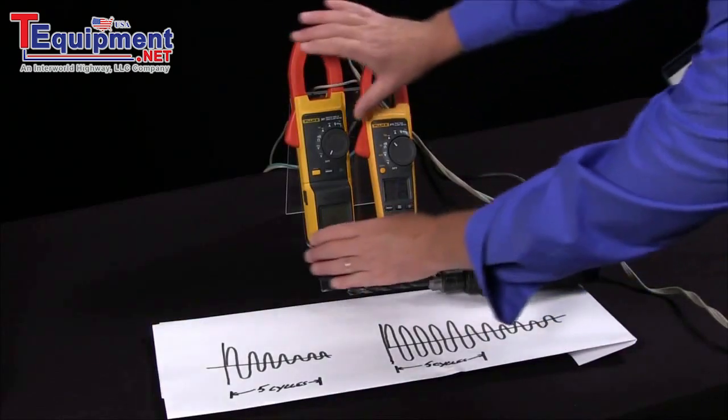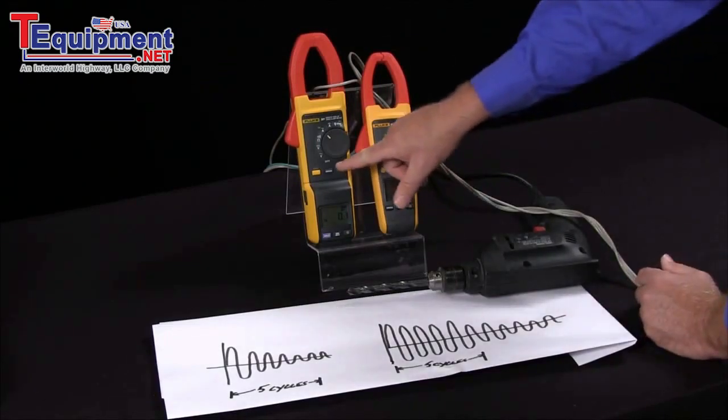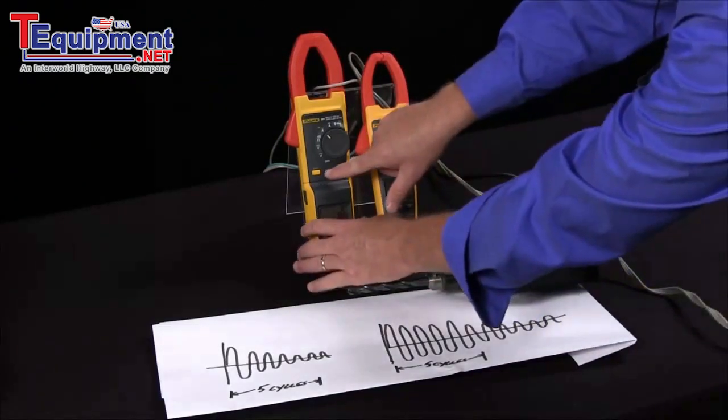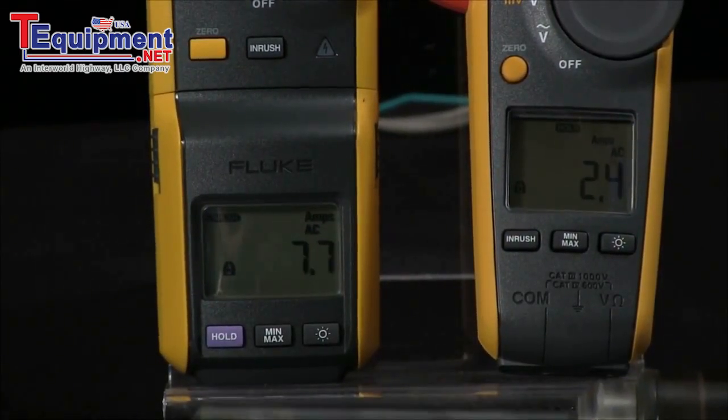Well, to take an inrush current I would turn on my meter to amps and I would need a clamp meter that has the ability to measure inrush. I hit the inrush button and then when my motor starts I can get the inrush current.